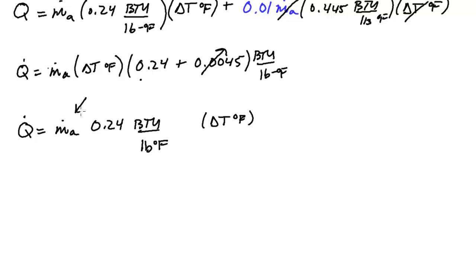So if we do this, we end up with something like this. Now, again, I said earlier, we typically don't deal in mass flow rate. We deal with volumetric flow rate. And so to do this conversion, we need density. So typically we want this flow in units of BTU per hour. So to make this all balance out, that would have meant that this pound per hour would be the units for this mass flow rate. So we need to go from pounds per hour to CFM or cubic feet per minute.